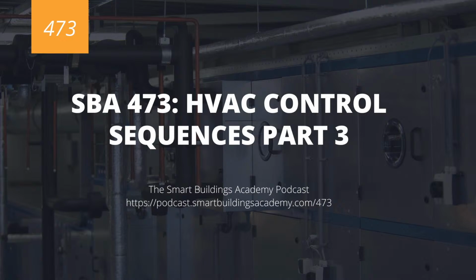So how this is going to work, I'm going to talk through some of the points. I'm going to talk through some of the things we're going to see in the systems, and that's what you can expect. So our primary thing with air handling units is moving the air volume, because that is how we are going to change temperature and humidity. Remember, our primary variable in all airside control is airflow. A lot of folks will say it's temperature. A lot of folks will say it's humidity. Some folks will even say it's CO2, but none of that matters if we aren't flowing air.